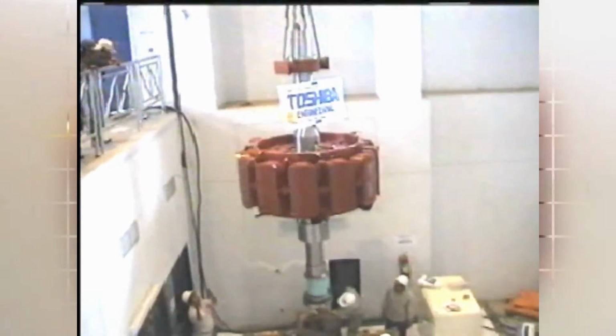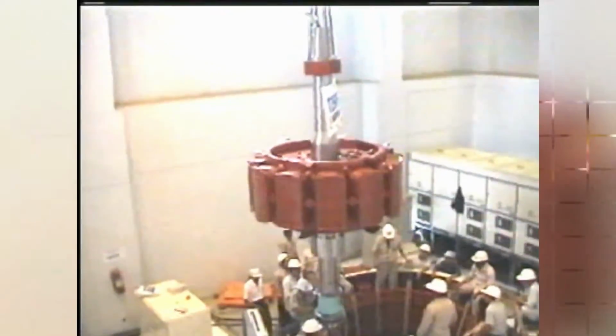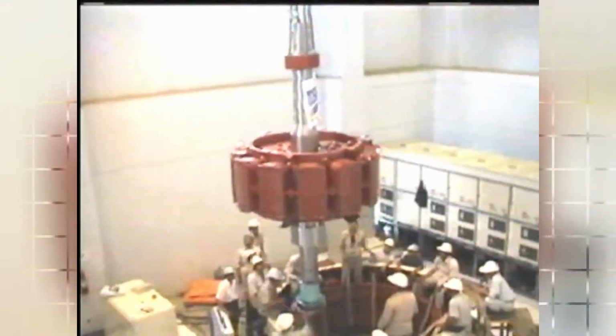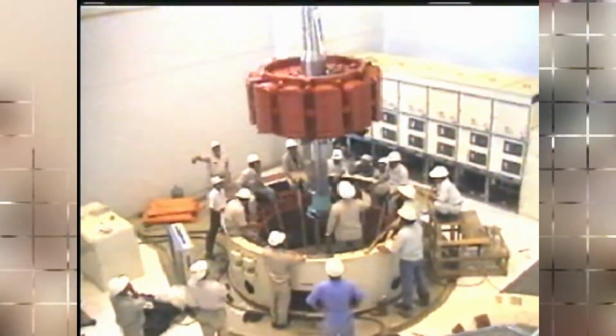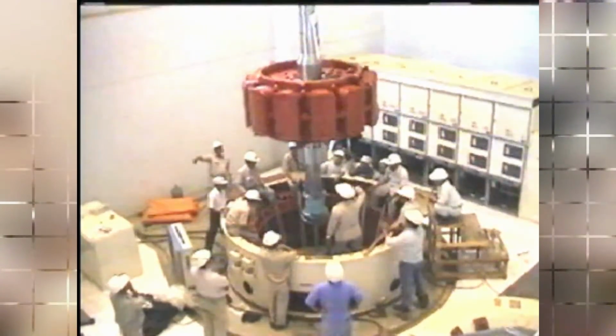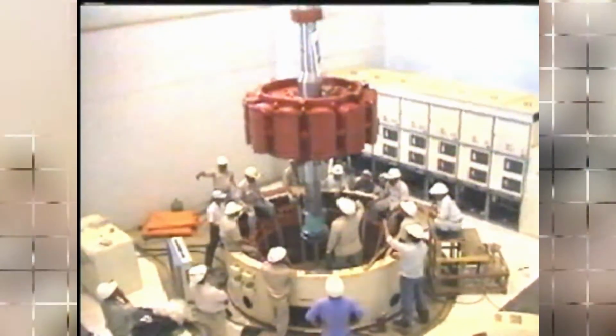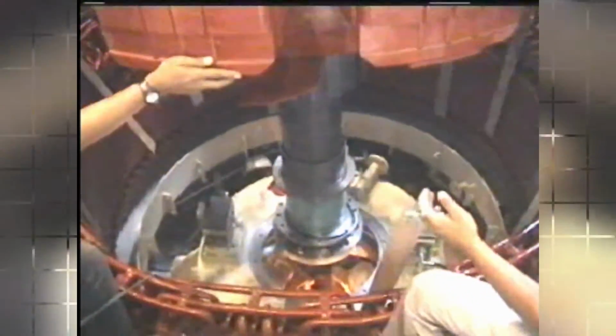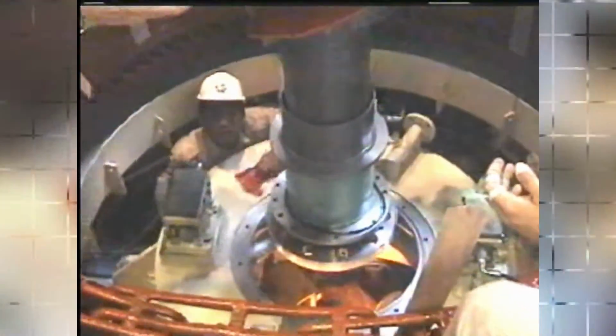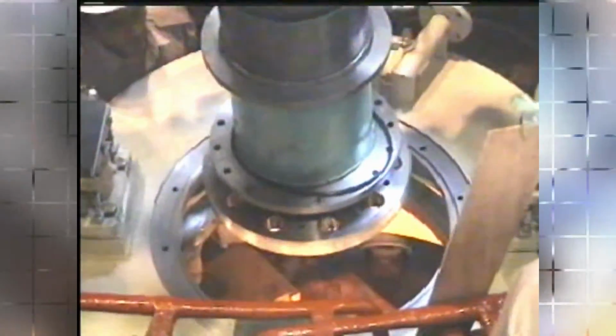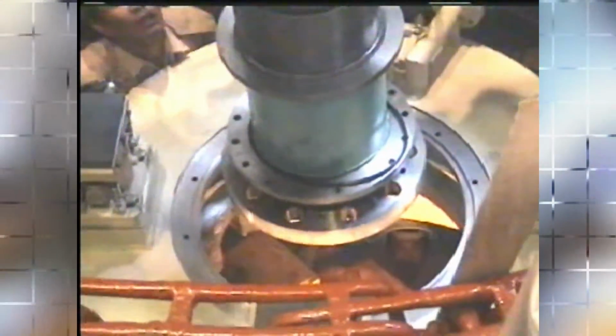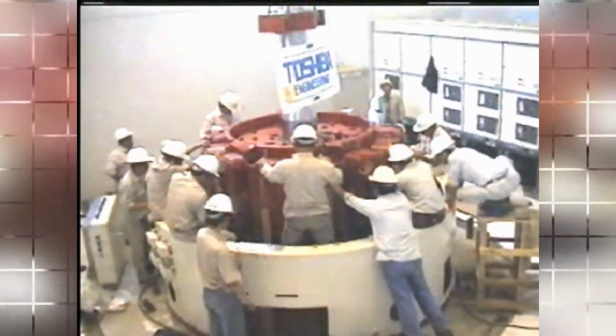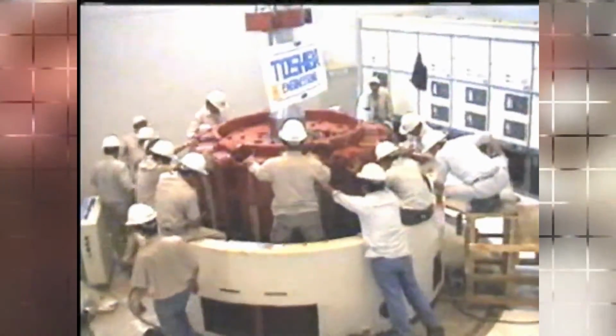Insulating collars are provided at the top and bottom of each field coil and adequately supported at all points. The inner or bottom insulating collar is supported in such a manner as to compensate for shrinkage in the insulation and to maintain adequate pressure on the field coil. The damper winding is sufficiently supported to eliminate mechanical failure due to vibrations, thermal expansion and contraction, or stresses from centrifugal forces throughout the speed range of the generator, including maximum overspeed.